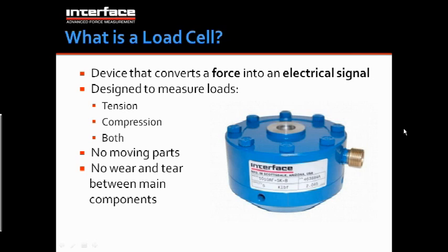So let's move on to what a load cell is. A load cell is a device that will convert a force into an electrical signal. This signal is proportional to the amount of load that is being applied to the load cell. Load cells are designed to measure loads in tension, loads in compression, and also a combination of both. The load cell has no moving parts, and therefore we have no wear and tear between the main components of a load cell.